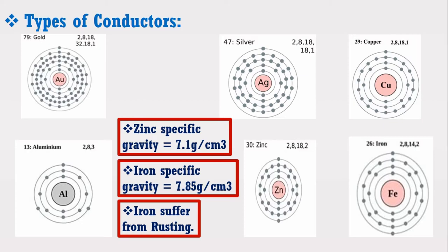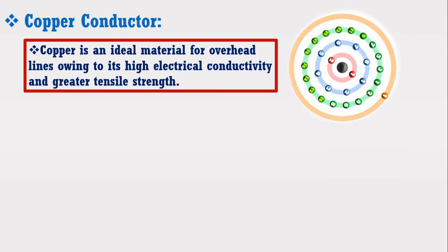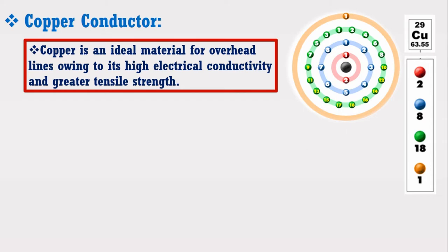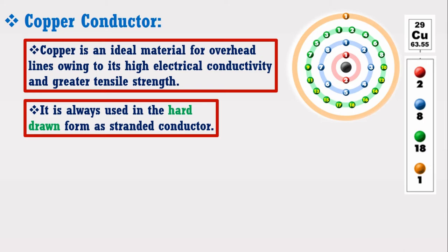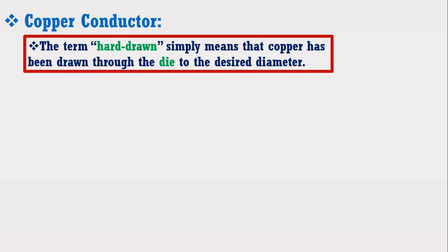From this discussion, we have only two choices — copper and aluminum — that can be used for overhead transmission lines. Copper is an ideal material for overhead lines owing to its high electrical conductivity and greater tensile strength. It has 29 electrons total with only one electron in its outer shell. It is always used in the hard drawn form as a stranded conductor. The term hard drawn simply means that the copper has been drawn through a die to the desired diameter.